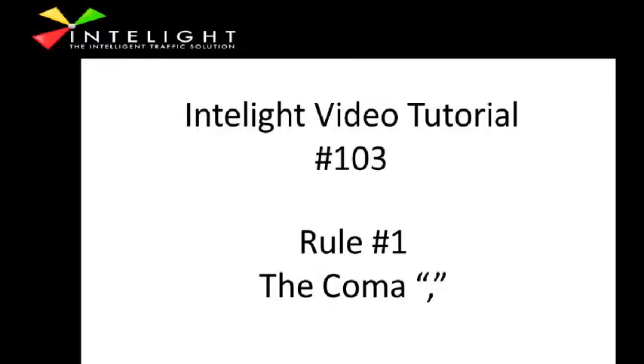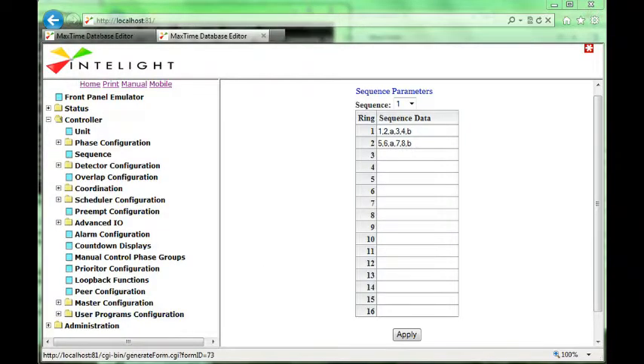The first rule in programming a sequence is the comma rule. We use the comma as our delimiter to separate phases and barriers, and you have to use a comma. The comma rule is very important. You have to use a comma, not a period, not a space. If you didn't have the comma between phases 1 and 2, it thinks it's phase 12. So make sure you use a comma to have a valid sequence.